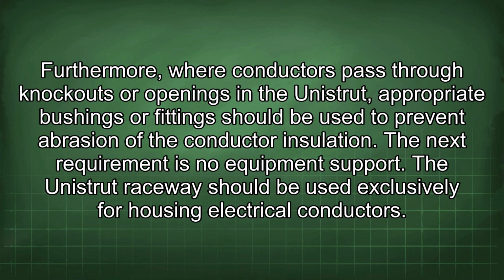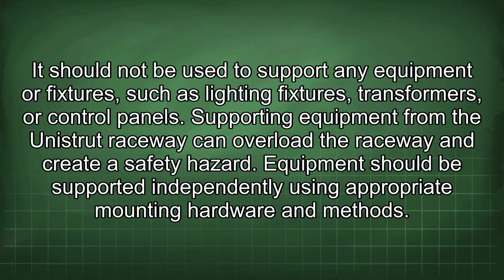The next requirement is no equipment support. The Unistrut raceway should be used exclusively for housing electrical conductors. It should not be used to support any equipment or fixtures such as lighting fixtures, transformers, or control panels. Supporting equipment from the Unistrut raceway can overload the raceway and create a safety hazard. Equipment should be supported independently using appropriate mounting hardware and methods.